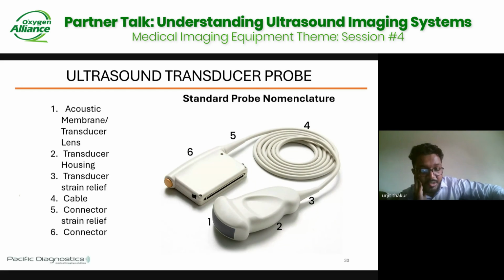Then you have the transducer housing, where the electrical cables are connected that send the signal into the piezoelectric crystal. The transducer strain relief is basically the rubber that prevents the cable from being damaged in case the transducer gets bent or you put it at certain angles.